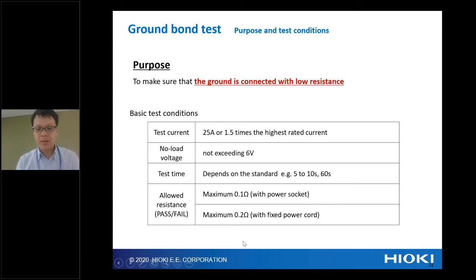So which part should we do the ground bond test? The test area, as you can see, is the red area. So the protective earth pole and areas where the protective earth is connected, for example, the metal enclosure and the screw, like that. These are the measurement points of the ground bond test.